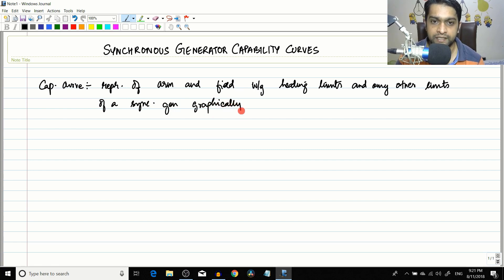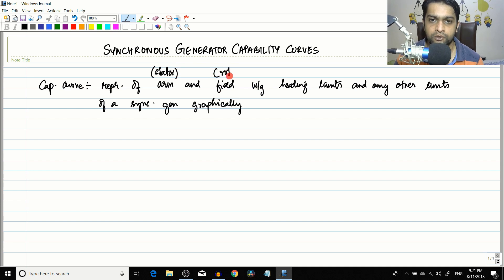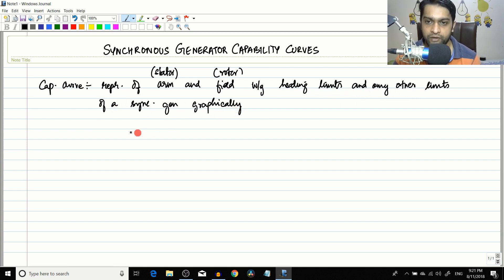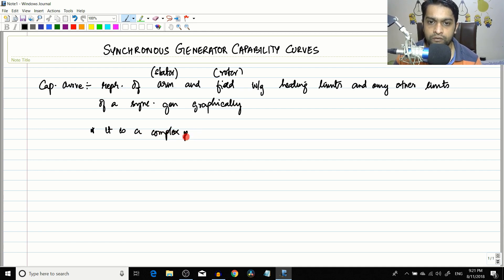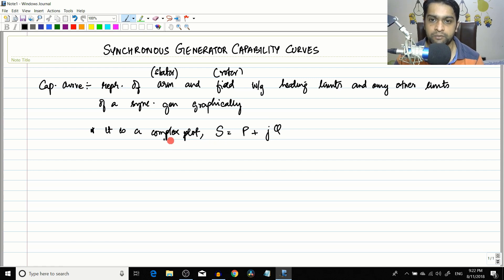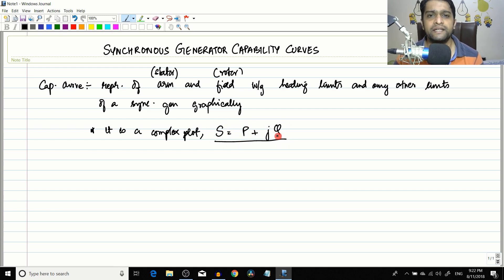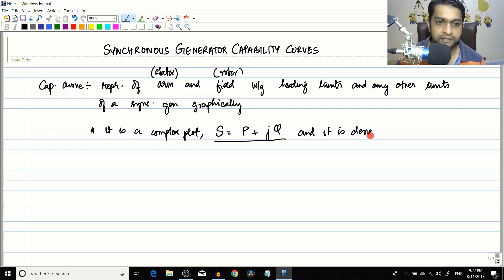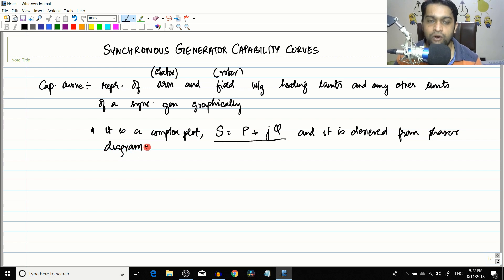As the statement suggests, it is going to be a graph. The armature is the stator and the field winding is the rotor, so it is a representation of stator and rotor winding heating limits graphically. Basically it is a complex plot of the kVA rating: S = P + jQ, where P is active power, Q is reactive power, and S is apparent power. It is derived from the phasor diagram of the synchronous generator.